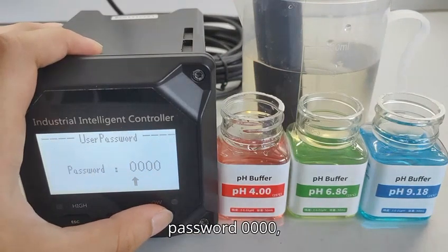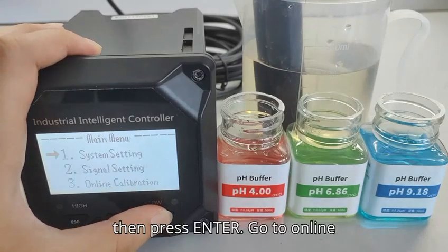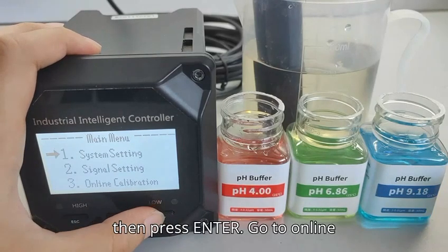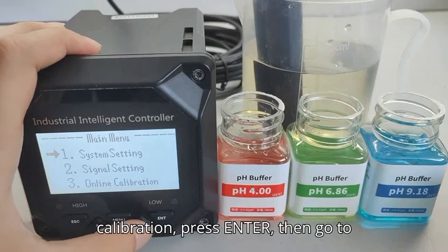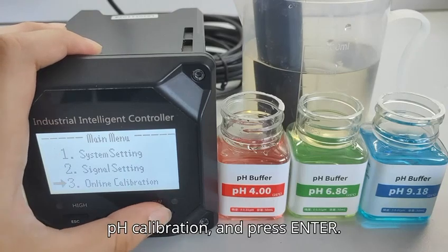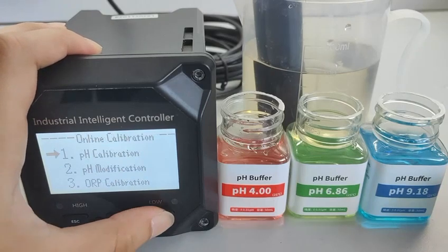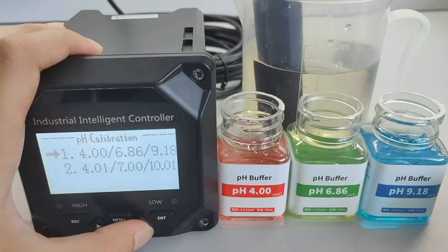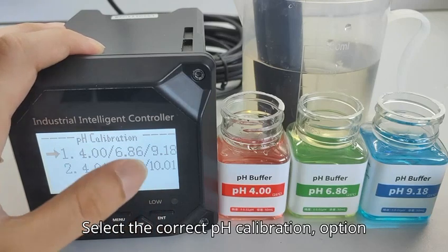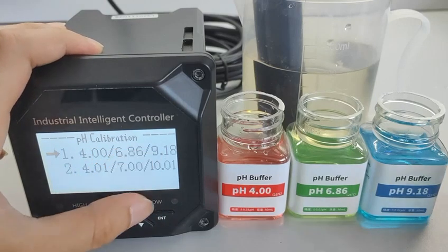Enter the password 0000, then press enter. Go to Online Calibration, press enter. Then go to pH Calibration, and press enter. Select the correct pH calibration, option 1 in this case.